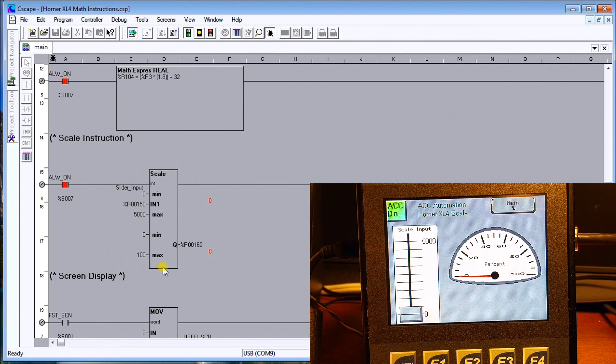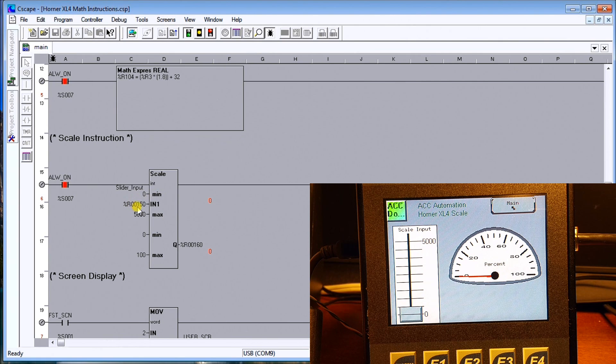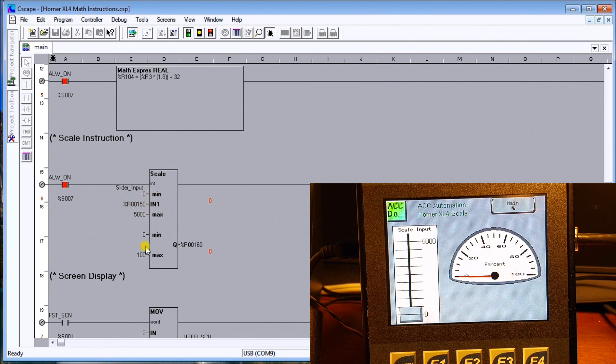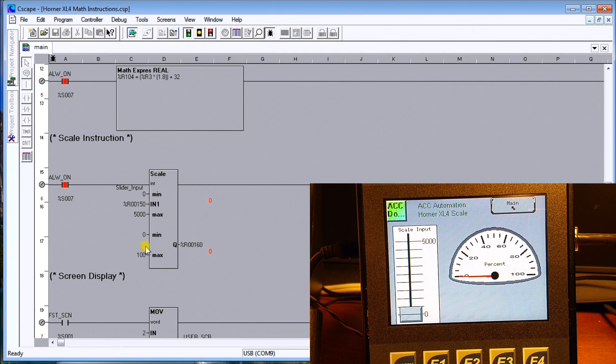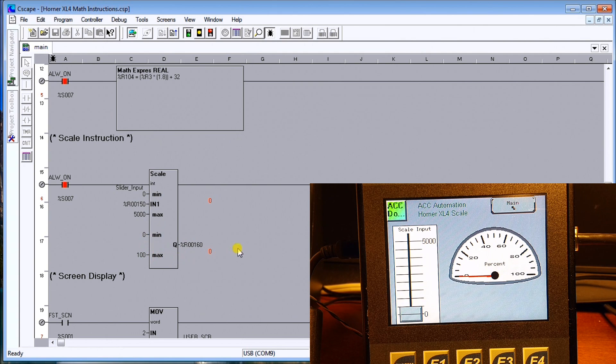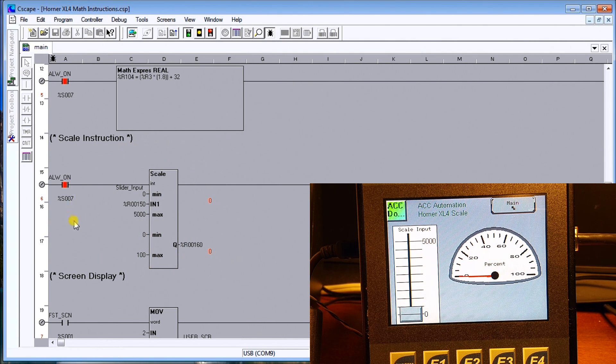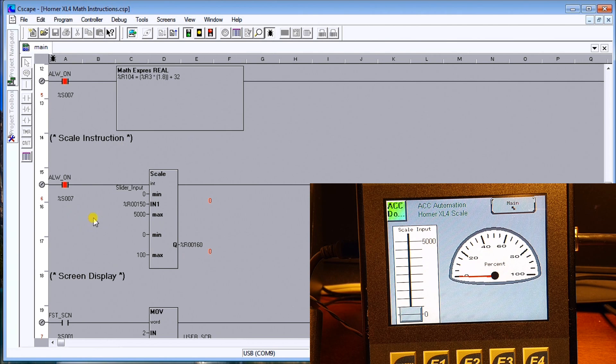So here is the actual instruction itself - you can see my input comes in here at zero to five thousand and my output is here zero to one hundred and it scales it between those two. So the instruction actually looks really good in terms of actually seeing what's happening.